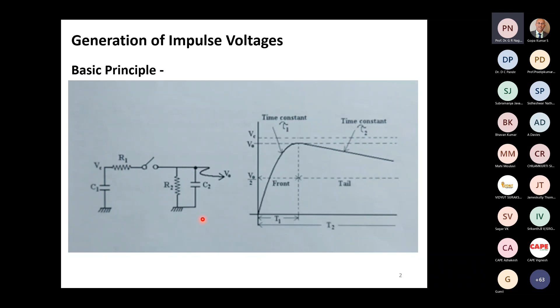Now, if you have got a single stage like this, it's not possible to go to what is the order of, say, 1 million volts or 5 million volts. It's not possible. If you think of a 220 kV power system, which is very, very common these days, the test volts are of the order of 1 million volts or more. So if you think of one capacitor here having 1 million volts, it's not practical. Therefore, what is done is this is split into many capacitors in series and then discharged through these capacitors to get the required wave shapes. Just to show the principle, this is known as the Marx generator.